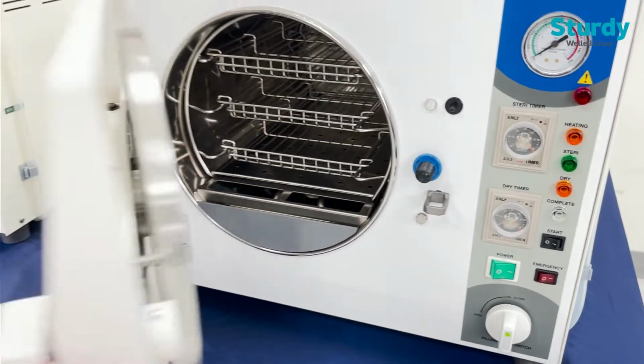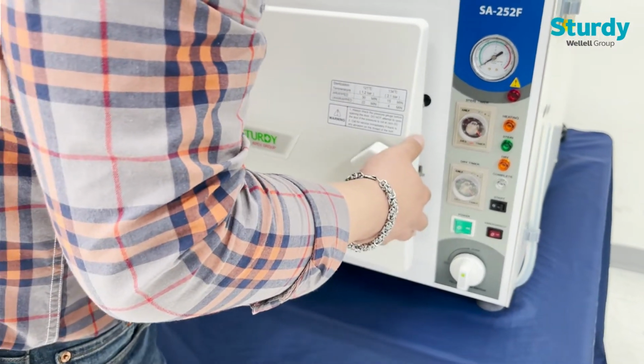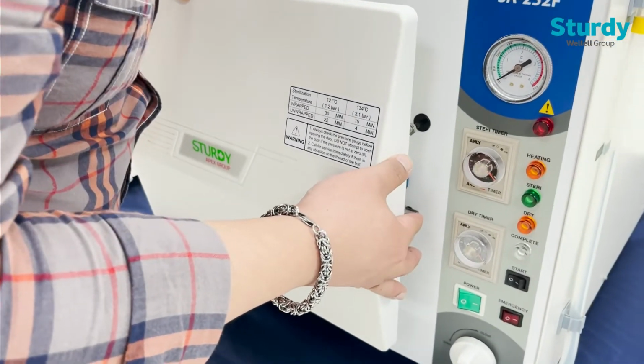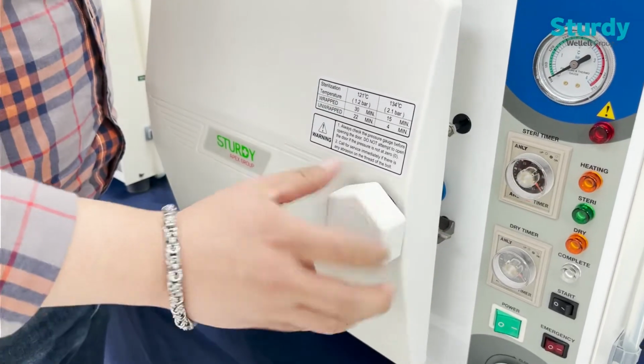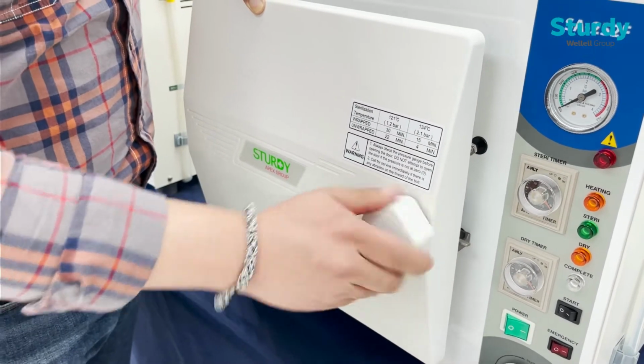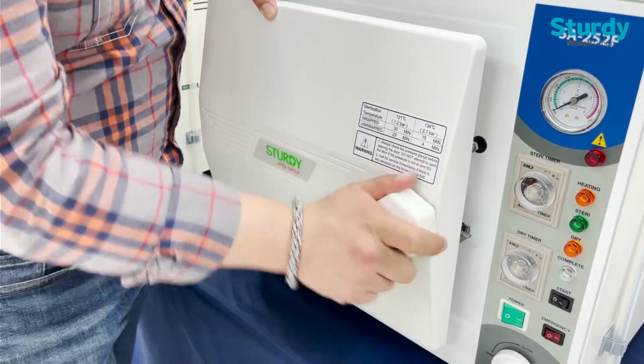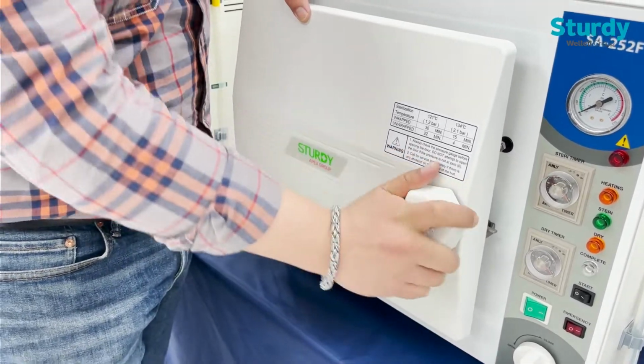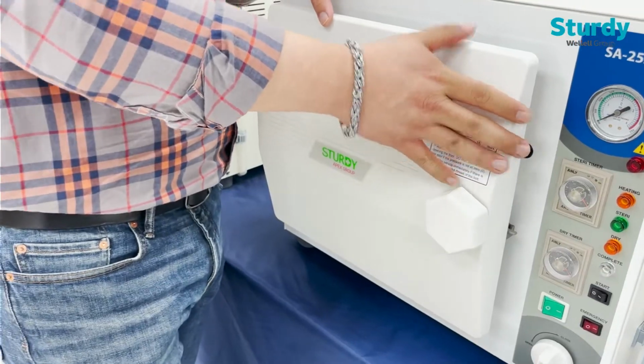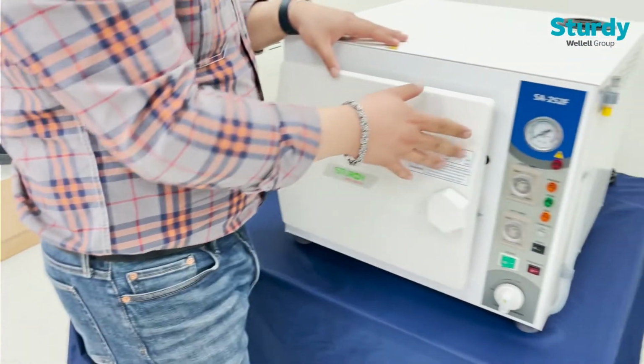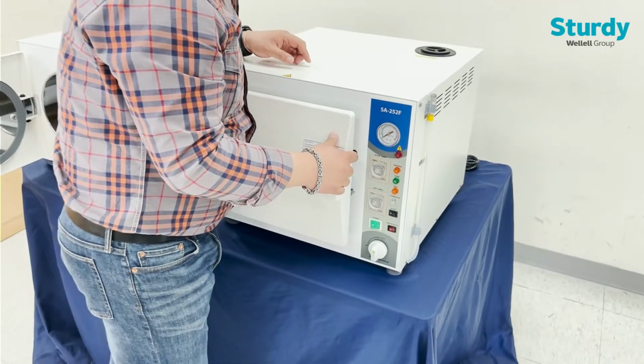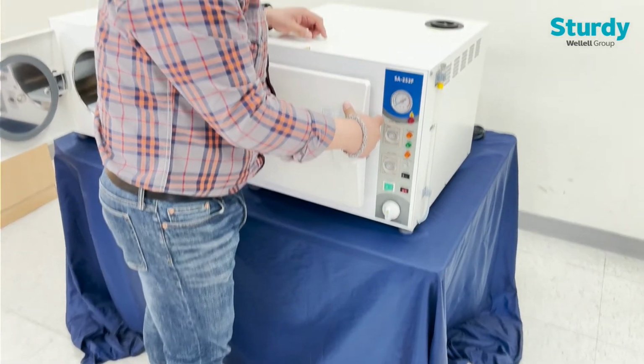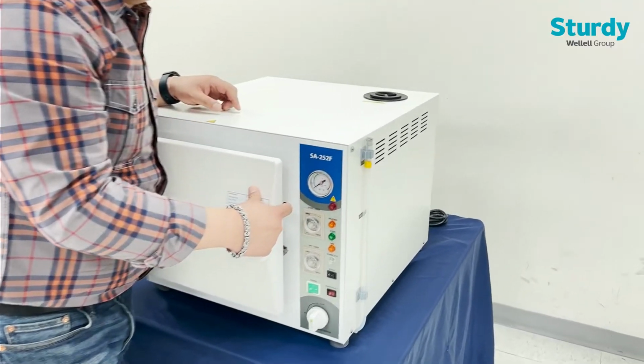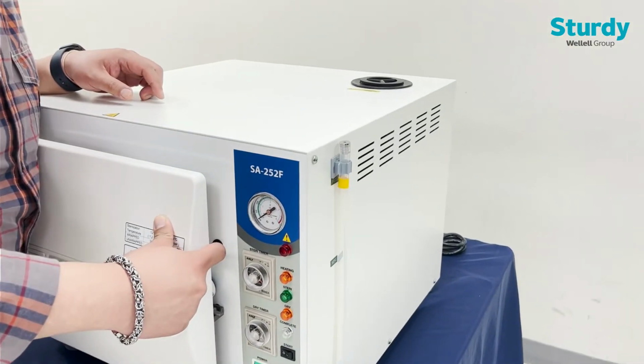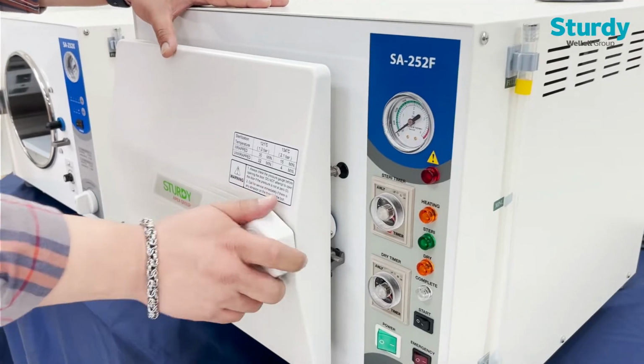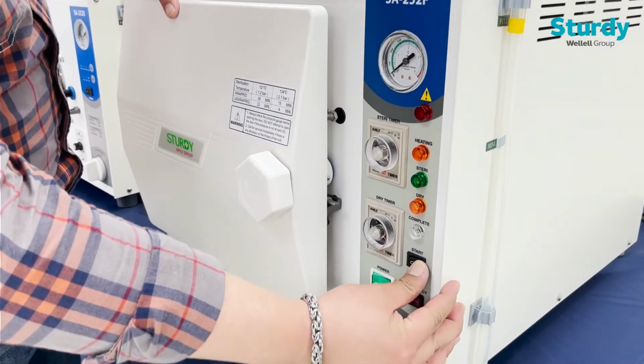Once that's set, we'll close the chamber door, lift up the safety hatch, and turn the handle clockwise right to the bottom until it's fully tightened. That means now the chamber door is closed. There is a safety mechanism behind the chamber door that will indicate that the door is fully closed properly. After that, simply press start.